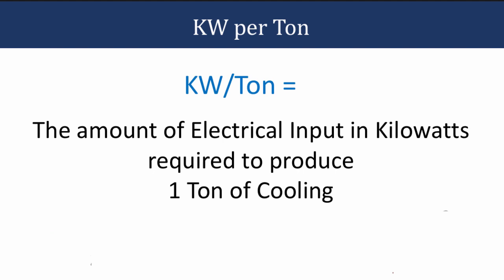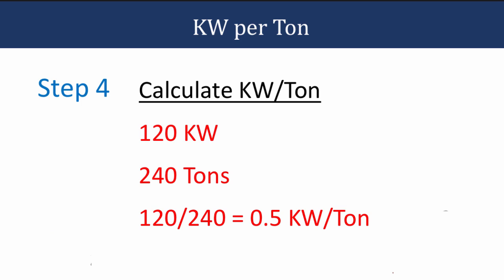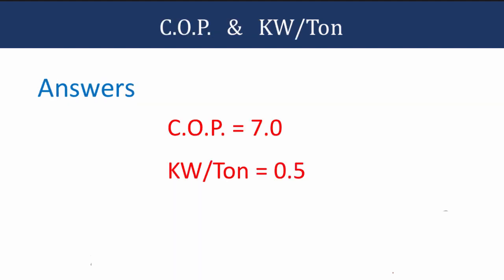Now let's get our KW per ton. KW per ton is the amount of electrical input in kilowatts required to produce one ton of cooling. The less power we put in to produce that tonnage of cooling, the more efficient the equipment is. To calculate KW per ton, we put the KW on top and the tons on the bottom: 120 KW divided by 240 tons gives us 0.5 KW per ton. So our COP is 7 and our KW per ton is 0.5.